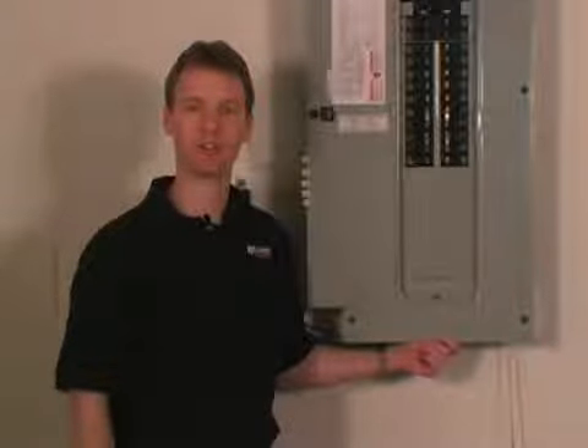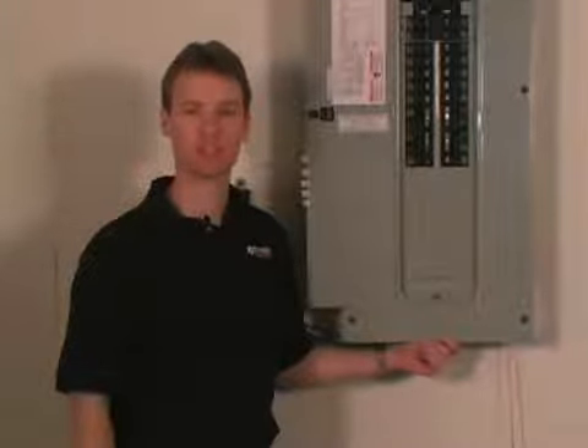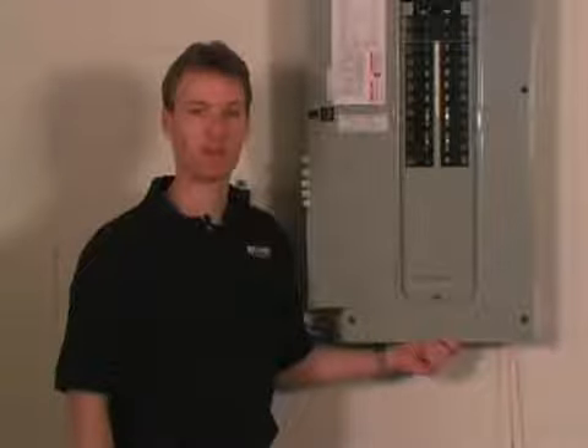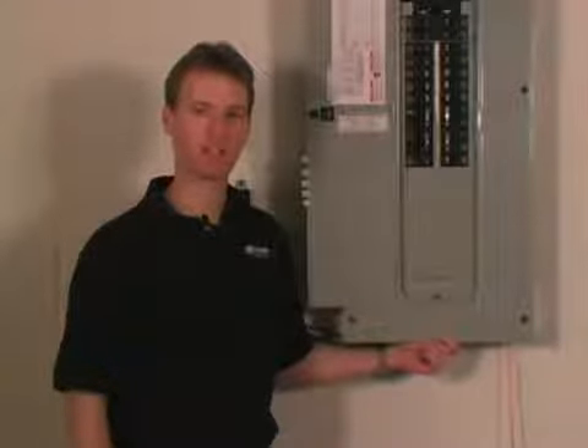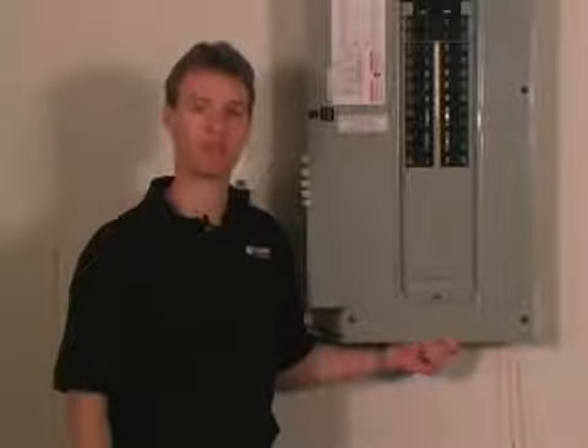After choosing the circuits we're going to power during an outage, we need to locate the corresponding circuit breakers and mark them in the main panel. We'll do this before we take the cover off the panel because it would be much more difficult to identify the breakers after the cover is off.